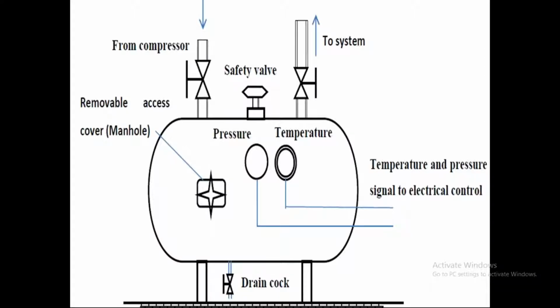All these inputs, the gas equations, we are using here. Once the volume is expanded for the given pressure from 7 bar to some 1000 liter or 2000 liter receiver, straight away the pressure gets stabilized within a few seconds. We want a non-pulsating pressure to be given to the process. We don't want a pulsating pressure to be given to the process.